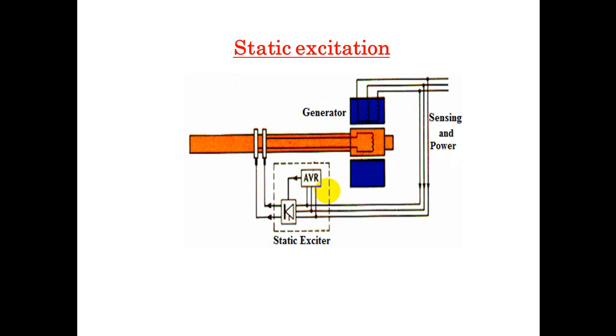In practice, second solution, the rectifier bridge. The rectifier bridge is supplied by a common three-phase source and not directly from the concerned generator itself. This applies in important distribution where several generators are in parallel. This method, or static excitation, is used in the distribution power stations, where several generators are connected in parallel. So the static exciter replaces the conventional excitation, with a diode that doesn't let the current go opposite into the generators.